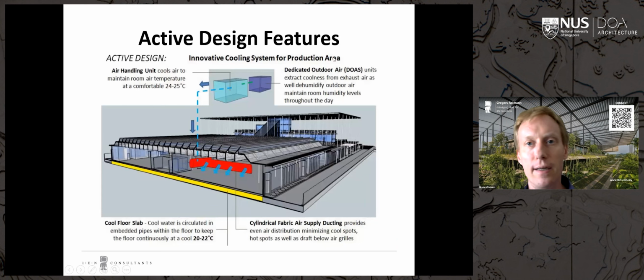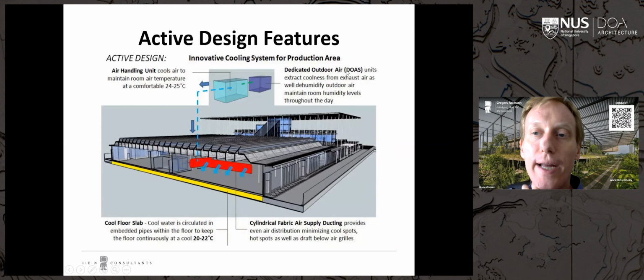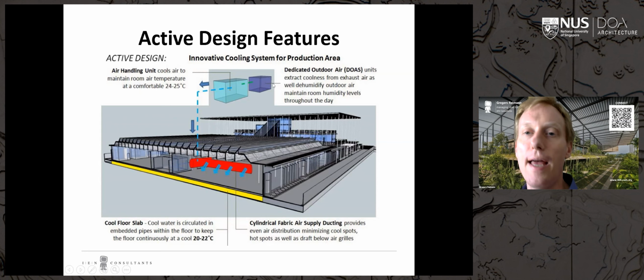On the active design side, some of the features we put in included a dedicated outdoor air system, meaning all the dehumidification of outdoor air was done in that system, along with energy recovery. So some of the exhaust from the factory allowed us to recapture some of the dryness from the air inside and transfer it to the incoming air. This way we could save about 30% of the energy for treating the outdoor air.